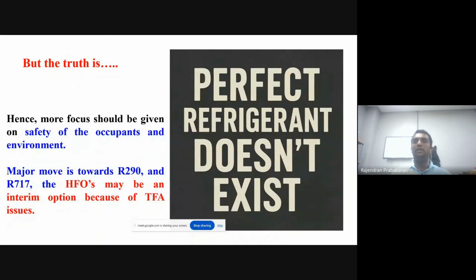We can see that the basic HFO refrigerants are ultra low GWP with slightly inferior performance, but okay to retrofit based on environmental concerns. But they have a TFA formation issue. It will affect water bodies because of acidic rain. On the other hand, ammonia is excellent in thermal performance with superior cooling and COP, but it is highly toxic. Similarly, R290 also has excellent thermal performance, but it is highly flammable.